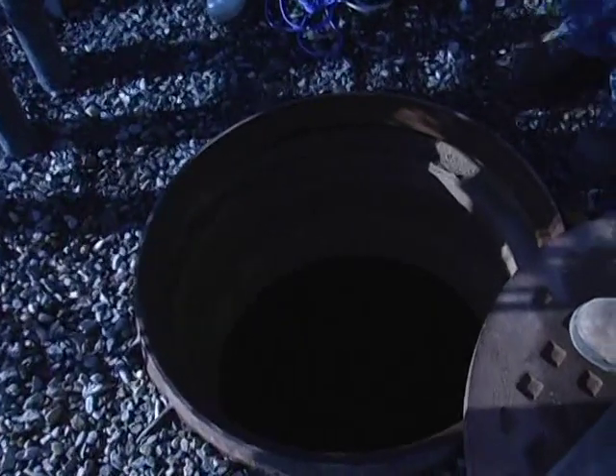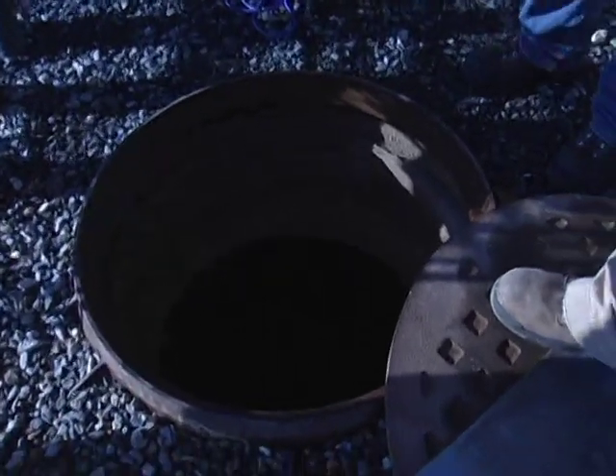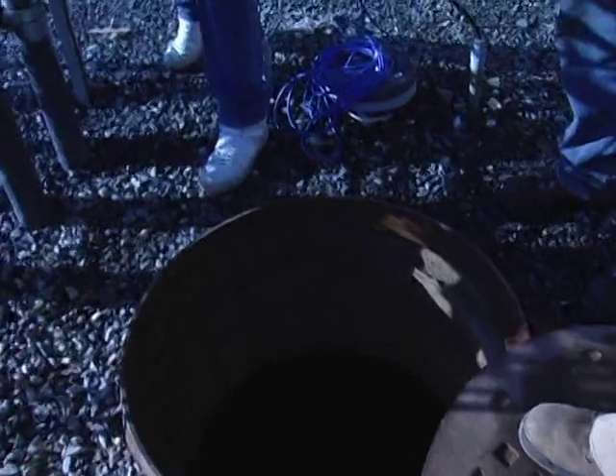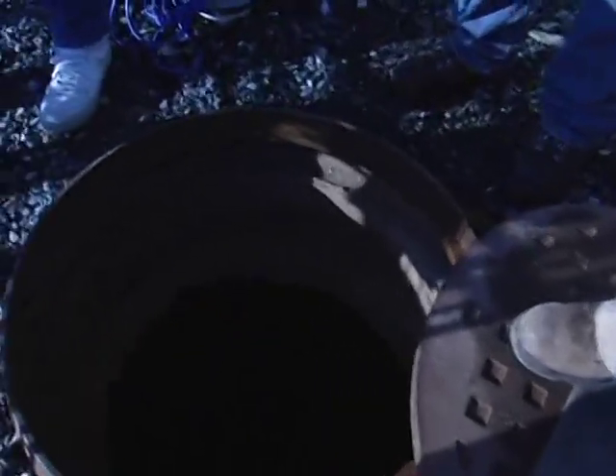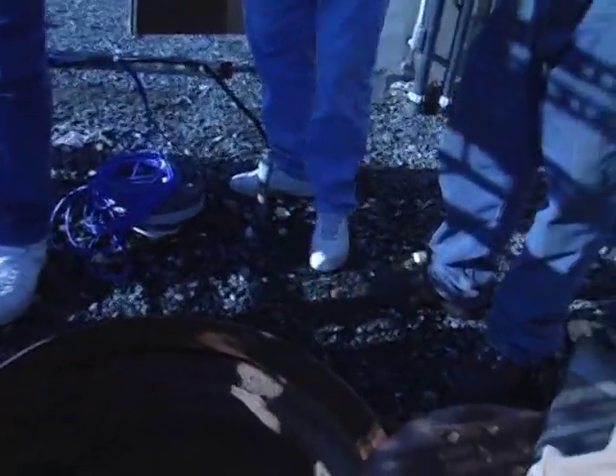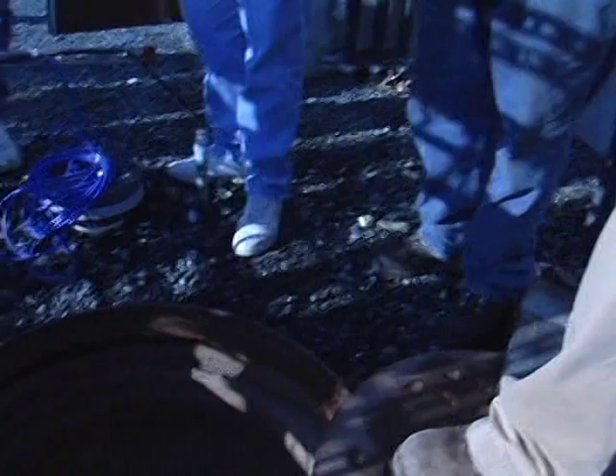What you're seeing is, you should never see water levels that are much higher than the overflow line that you see there that goes into the waste sump adjacent to it. And you have a duty and a standby pump, powered by these panels here. There's a hand and an auto function, as well as a function in the SCADA system where you can switch between the duty and the standby pumps.